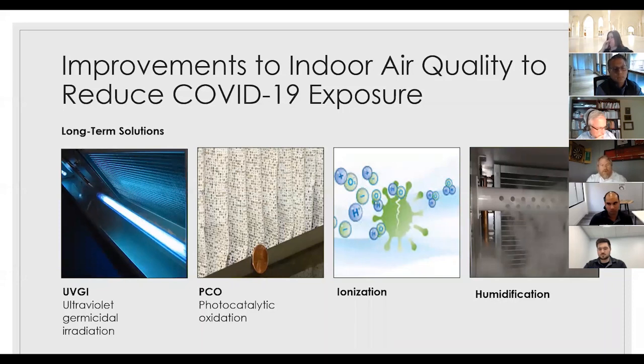It works really well in air handling units. It works and is most effective at about 500 feet a minute, which, for the facilities folks, is the general velocity that air handling units operate at. It can be added to return air duct streams or supply air duct streams. It just needs more thought put into the duct configuration. It may take a little design to make sure it functions as efficiently as it should. I'd be happy to talk to anybody about that one. That takes a little deeper dive after the presentation.